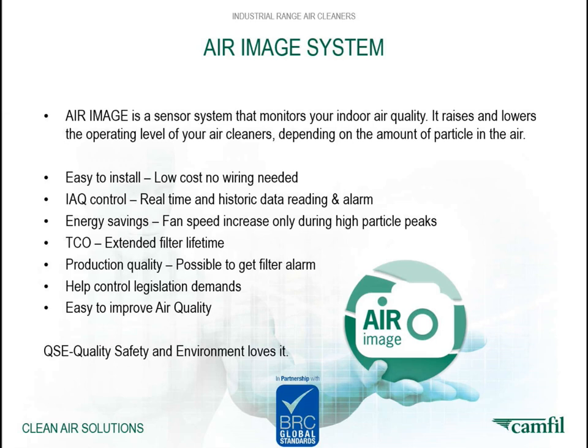Some of the benefits are: easy to install, low cost, no wiring needed, indoor air quality control, real-time and historical data reading, an alarm in the user interface for filter replacement, and energy savings. Fan speed increases only during high particle peaks.